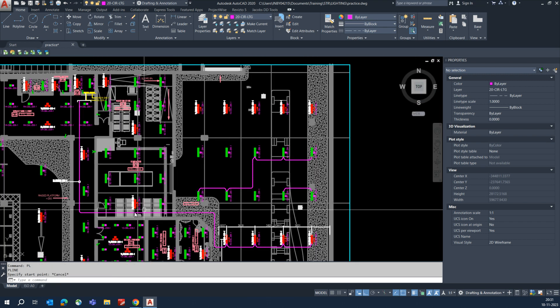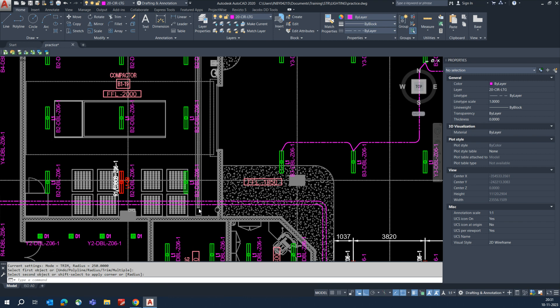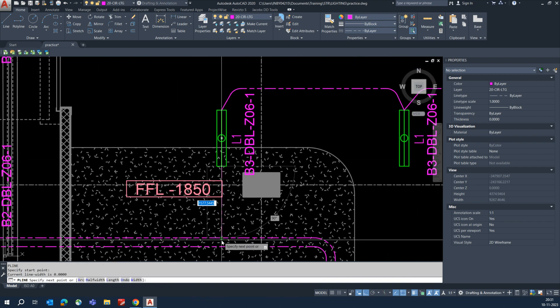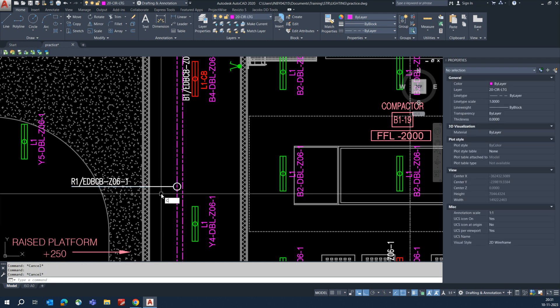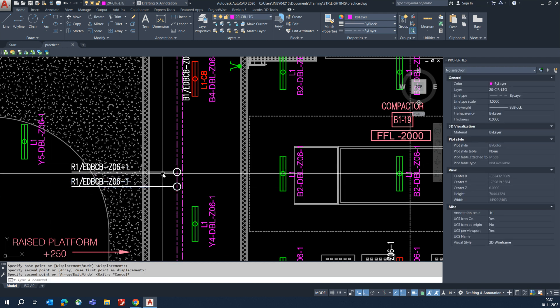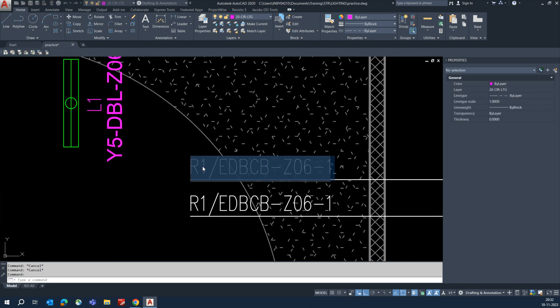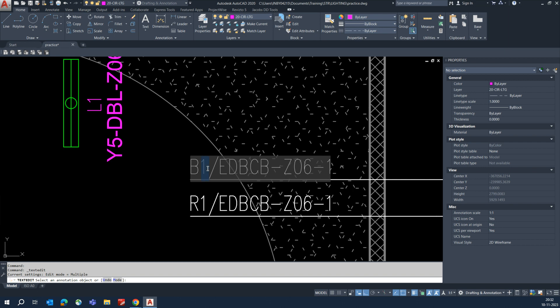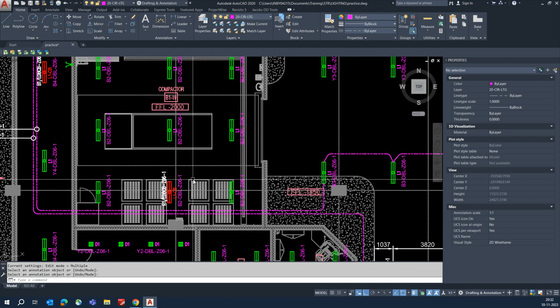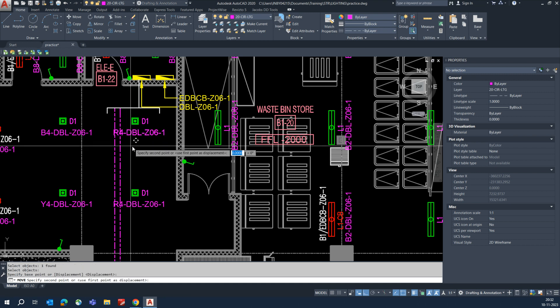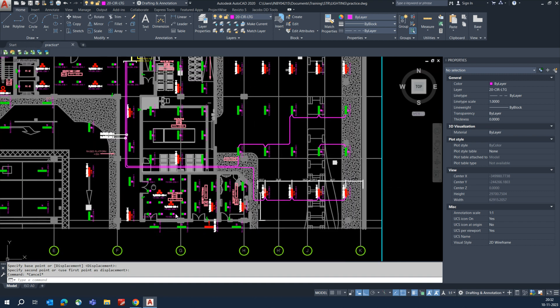Give an offset of this line so it goes at the same distance. Connect from this one to that one and fillet it — that means another circuit is going through. Mention the circuit number here. Stretch and change the circuit number to B3. The B3 circuit number is coming from here, going to and connecting to the DB. Avoid clashing with all the text and everything while drawing.